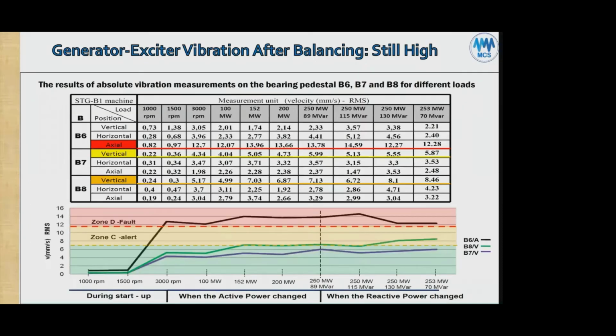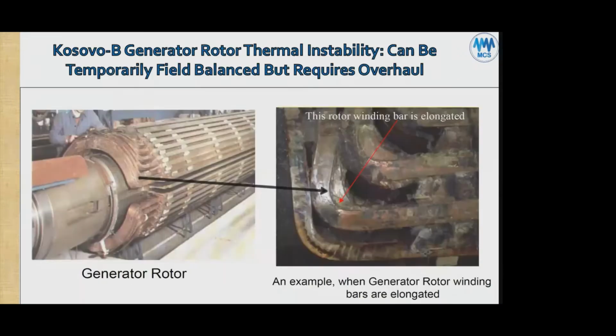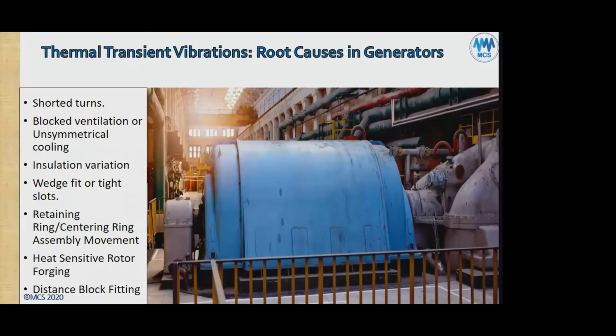However, as we said, there's a heavy misalignment in this machine between the generator and the other driver, which would be the LP turbine. The LP turbine is bolted to the generator, so there's definitely a misalignment occurring. Are there other issues involved? I don't know exactly in this case. It could be there are bearing issues they're not aware of. It could be other issues, because when we see failure analysis on vibration reports, sometimes the person has not captured all the causes. Okay, so if we come to thermal transients, vibrations caused by thermal transients, what are the root causes in generators?